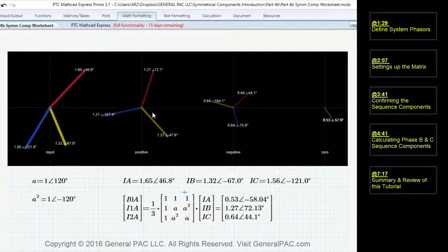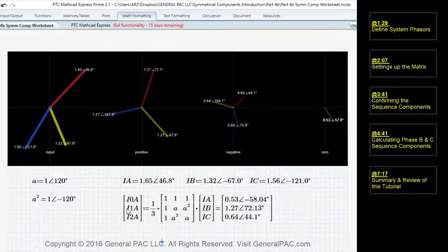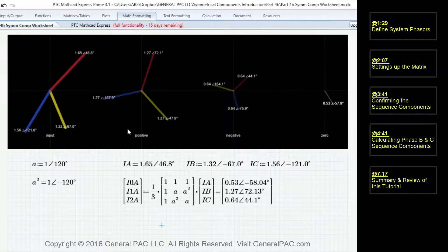The zero sequence component is equal to 0.53 at negative 57.9 degrees. The positive sequence component for phase A — our reference phasor — is equal to 1.27 at 72.13 degrees. And the negative sequence component for our reference phasor is equal to 0.64 at 44.1 degrees. It's very important to note that when we take the A-inverse matrix and multiply to get the sequence components, what we get are the reference phasors defined as phase A: zero sequence for phase A, positive sequence for phase A, and negative sequence for phase A.